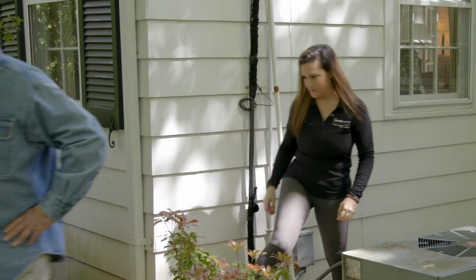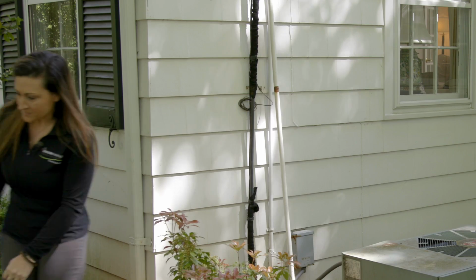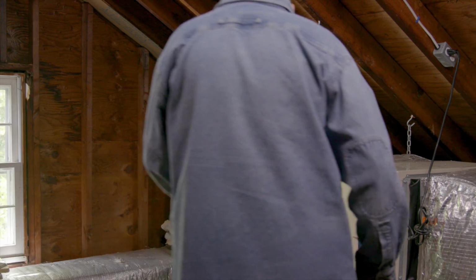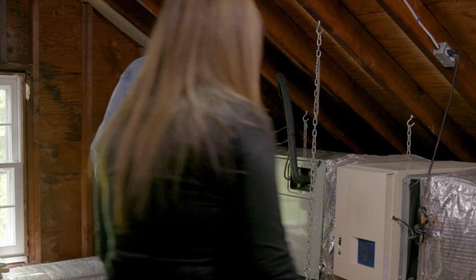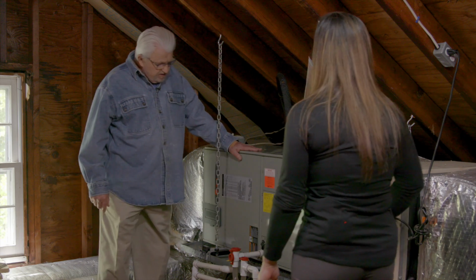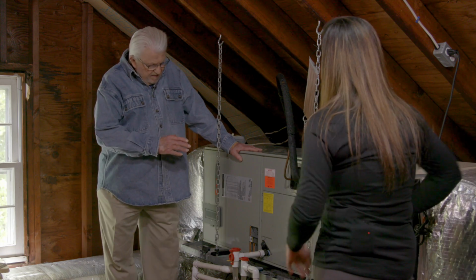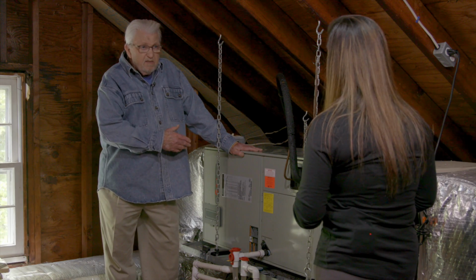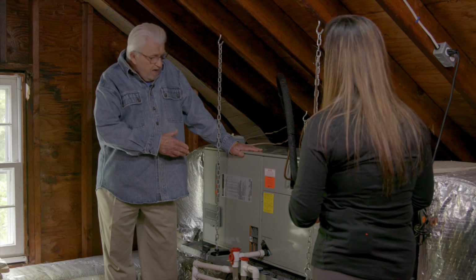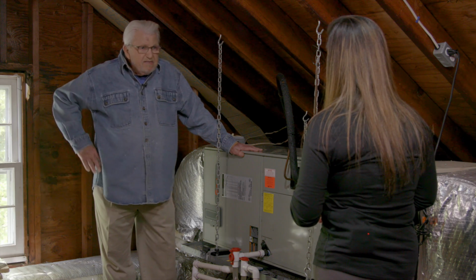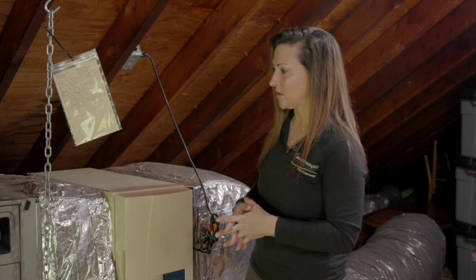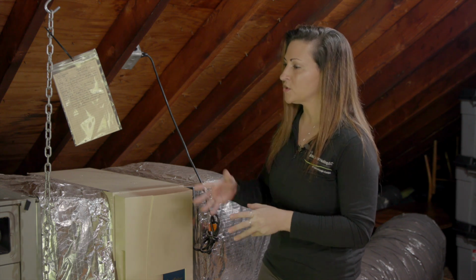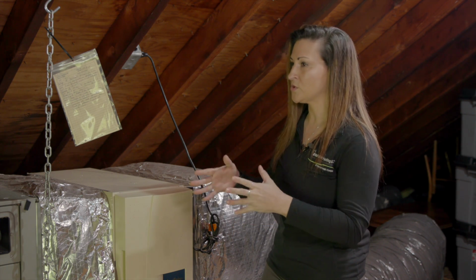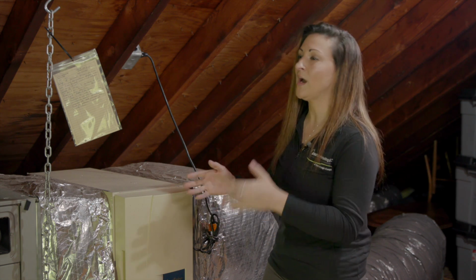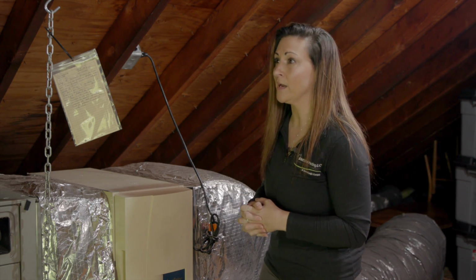With that, Jen and I head up to the attic. Well, obviously we're in the attic here, Jen, and here's the existing air handler. Now, this is not nearly as old as the condenser outside. Is it necessary to replace this? It's typically not necessary, but in your case it will be, just because it runs on R22, a refrigerant that is now obsolete. You have to replace them both so they can be compatible with each other.